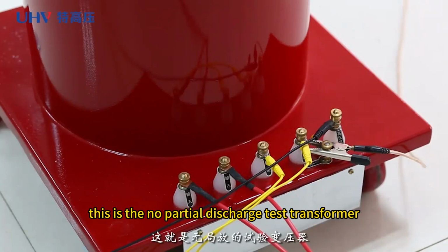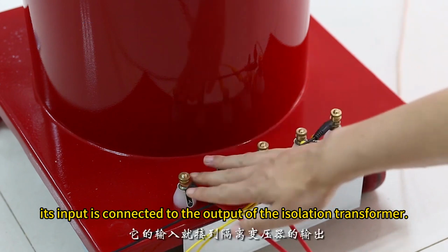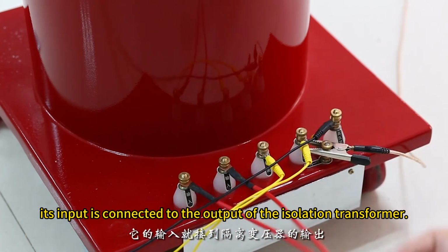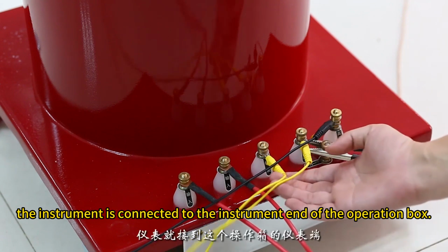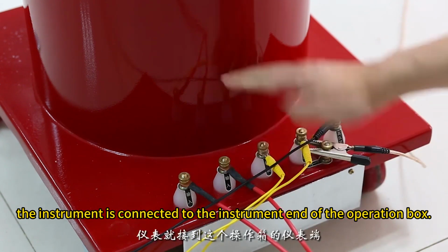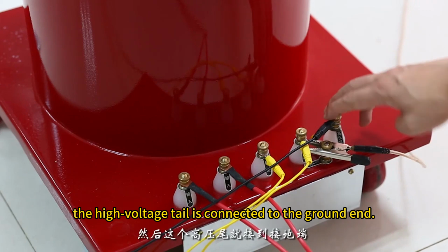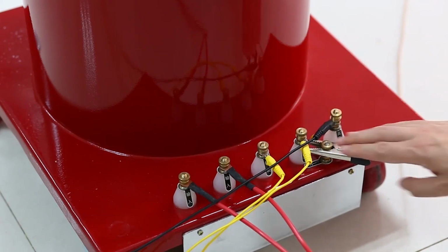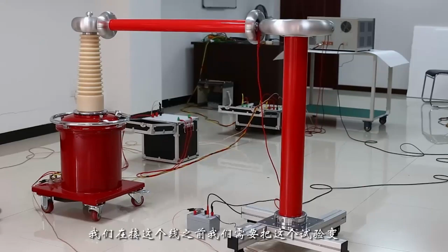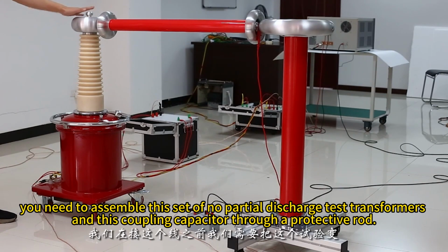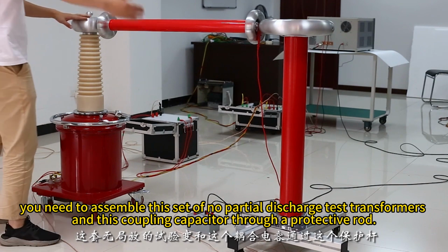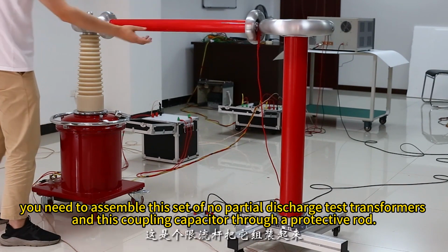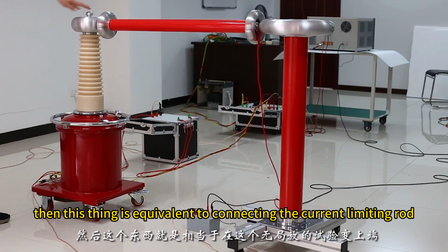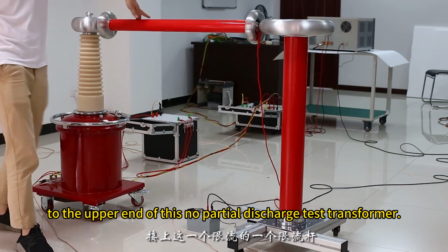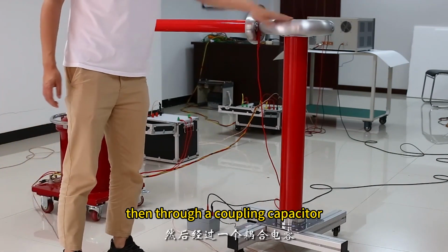This is the no partial discharge test transformer. Its input is connected to the output of the isolation transformer. The instrument is connected to the instrument end of the operation box. The high voltage tail is connected to the ground end. Ground the instrument. Before connecting this line, you need to assemble this set of no partial discharge test transformers and this coupling capacitor through a protective rod. Then this is equivalent to connecting the current limiting rod to the upper end of this no partial discharge test transformer, and then through a coupling capacitor.